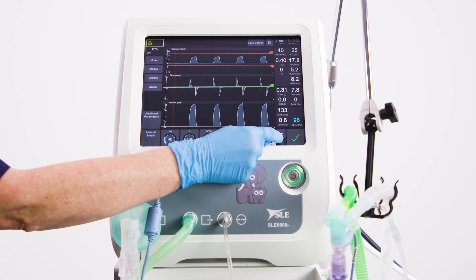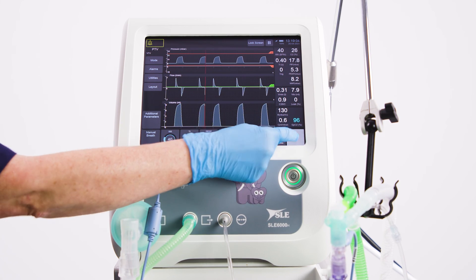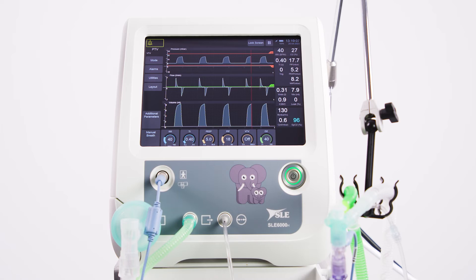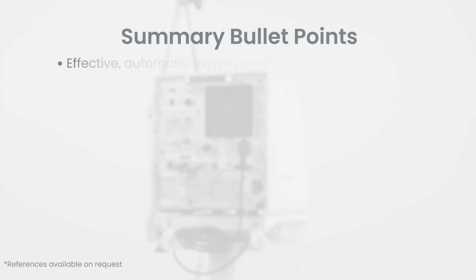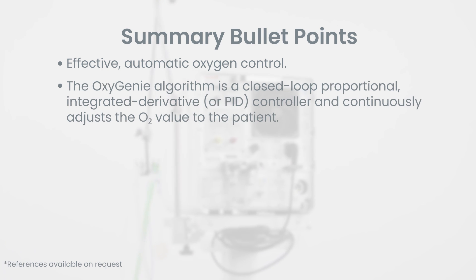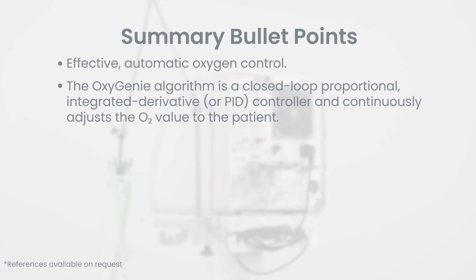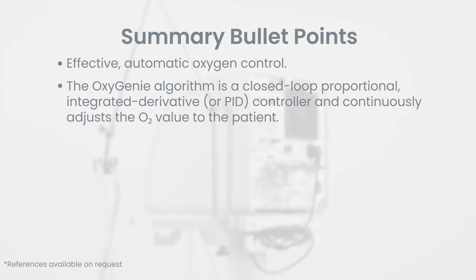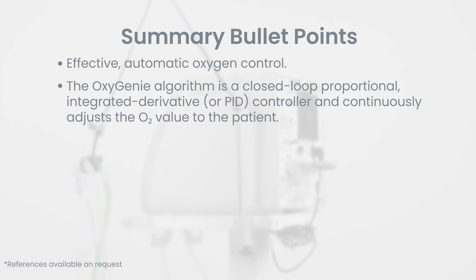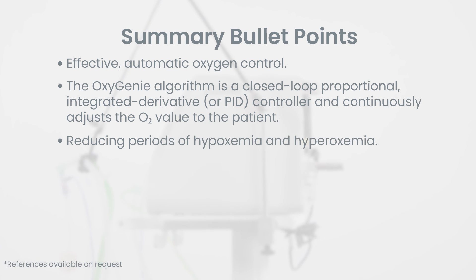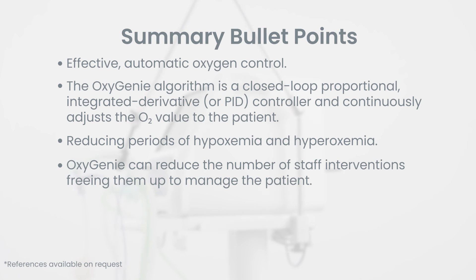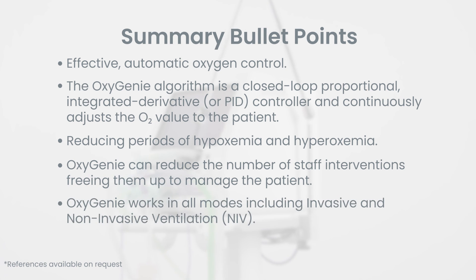Once OxyGenie is stabilised, it can be re-commenced and a new appropriate reference value will be set. The OxyGenie algorithm is a closed-loop proportional integrated derivative, or PID, controller and continuously adjusts the O2 value to the patient, reducing periods of hypoxemia and hyperoxemia. OxyGenie can reduce the number of staff interventions, freeing them up to manage the patient. OxyGenie works in all modes, including invasive and non-invasive ventilation.